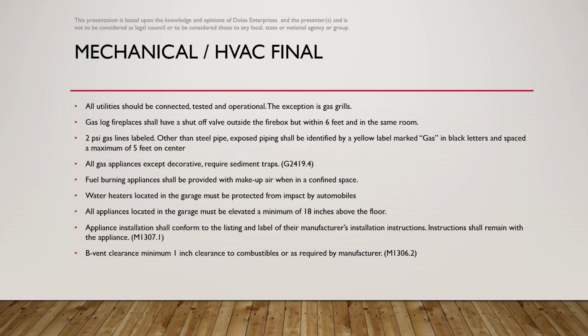All gas appliances except decorative are required to have sediment traps. Fuel burning appliances shall be provided with makeup air when in a confined space. Water heaters located in the garage must be protected from impact by automobiles. All appliances located in the garage must be elevated a minimum of 18 inches above the floor. Appliance installations shall conform to the listing and the label of their manufacturer's installation instructions. Instructions shall remain with the appliance. B-vent clearances of 1 inch to combustibles is required or as otherwise required by the manufacturer.